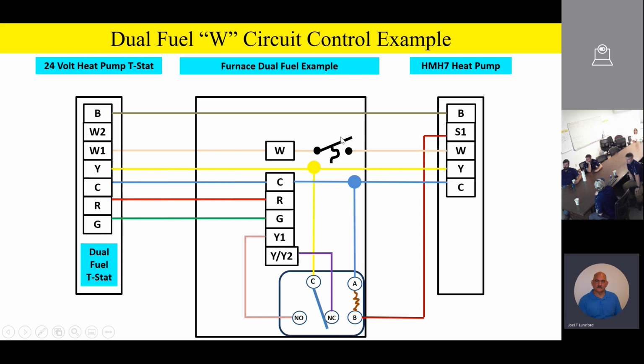And what's going to happen, this switch right here will close on a drop of temperature, and it'll bring the auxiliary heat on after maybe a minute or so once you're into defrost. Once you come out of defrost and you're back in the heating mode, remember, on a heat pump, the indoor coil is the condenser in the heating mode. So when it goes back into the heating mode, that suction line is going to get real hot pretty quickly because it's the hot gas line in the heating mode, right? And so what'll happen, this switch will open pretty quickly when it goes back into the heating mode.